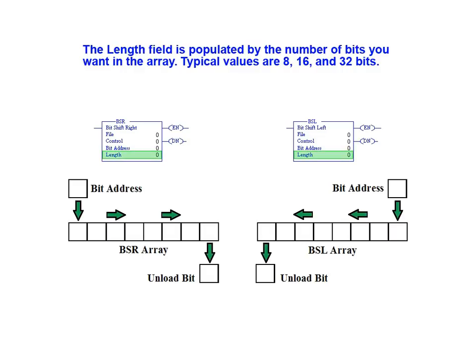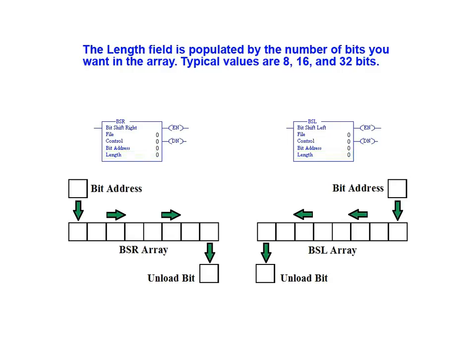The length field is populated by the number of bits you want in the array. Typical values are 8, 16, and 32 bits. The BSR and BSL instructions work in the same way. The shift direction and locations at which data is shifted in or out is the significant difference between these two instructions.